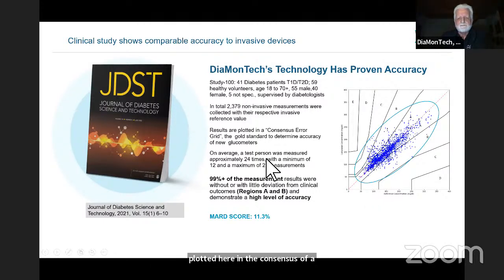And you see that about 99% of the measurements are within the regions A and B, which means little or no deviation from clinical outcomes. And this level of accuracy, which corresponds to a mean error of about 11%, is comparable to minimally invasive standard devices here. So the principle works fine.